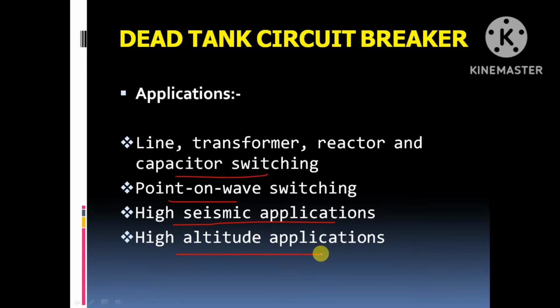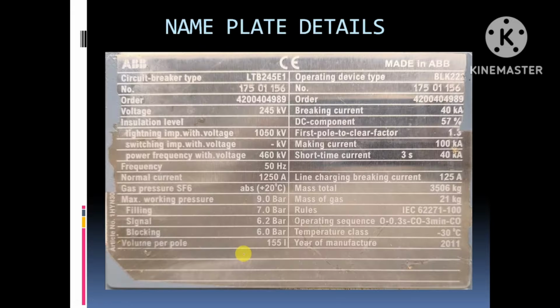And also it is advantageous for high altitude applications, where hilly area, if any substation or any station is there, then this type of circuit breaker is more stable compared to the live tank circuit breaker, because in the live tank circuit breaker the entire weight is on the top side above the ground, whereas in the dead tank the entire weight will be on the ground level, so it is more stable.